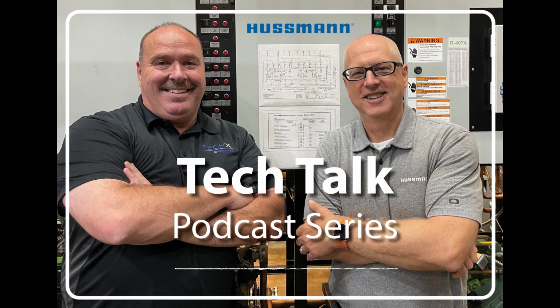Paul, you're correct. Mechanical failures can be just as disrupting. Lack of airflow can be caused by fan motor failure. Larger air-cooled condensers are usually direct drive, but the other system to look for is a V-belt and pulley, otherwise known as a sheave system. For this podcast, we'll be referring to it as a pulley system.